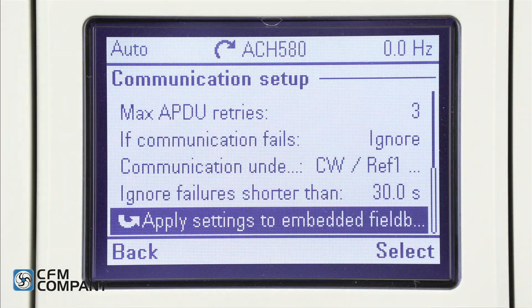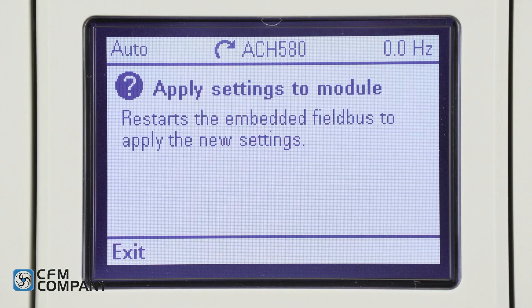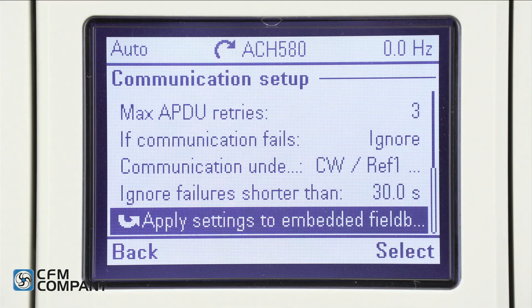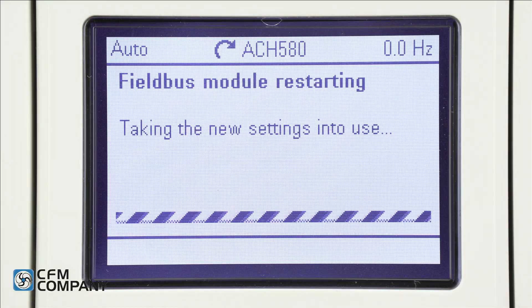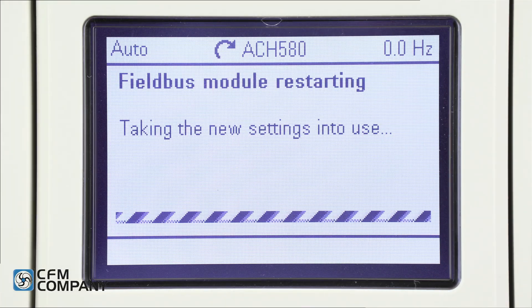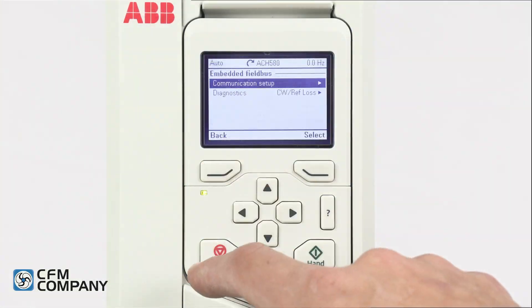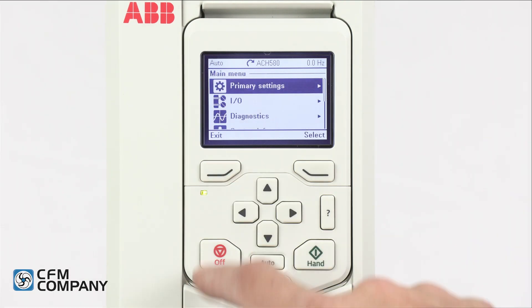The last setting is apply settings to embedded field bus. Press the question mark button. This restarts the embedded field bus to apply the new settings. As with most serial communication devices, the ABB ACH 580 requires a restart to apply the new settings. Press exit to return to the communication setup menu. After select is pressed, the drive will display: field bus module restarting, taking new settings into use. Once complete, the BACnet is programmed. Press the back button five times to return to the home screen.